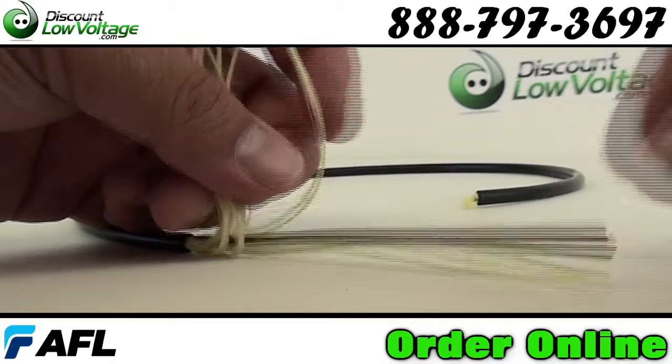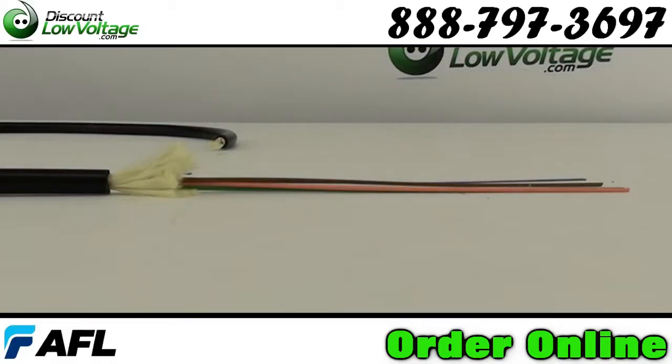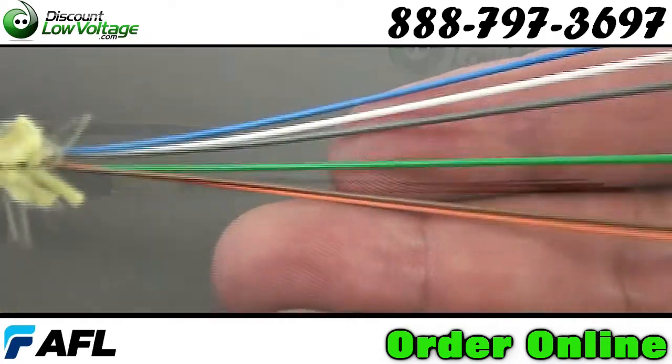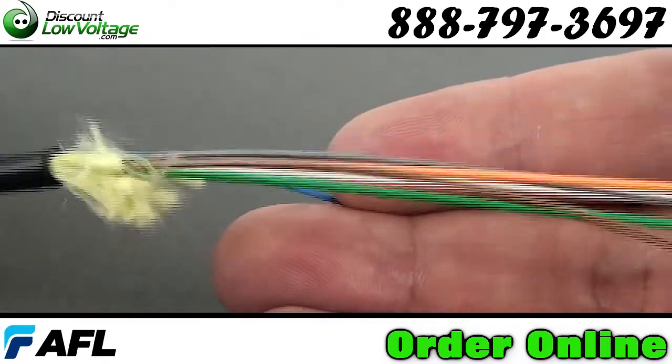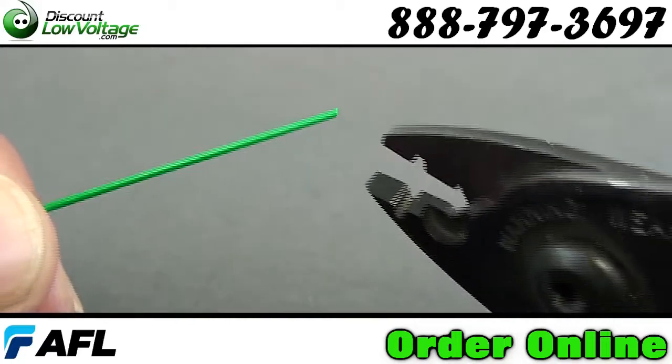With its riser rating, this cable can be used indoor and outdoor. Cables are water-blocked and meet water penetration requirements of GR-20-CORE. This helps ensure that any damage of the cable is restricted to a repairable length of several meters. It's also MSHA approved for mining applications.